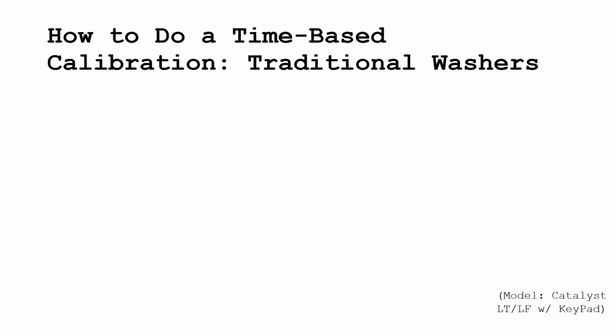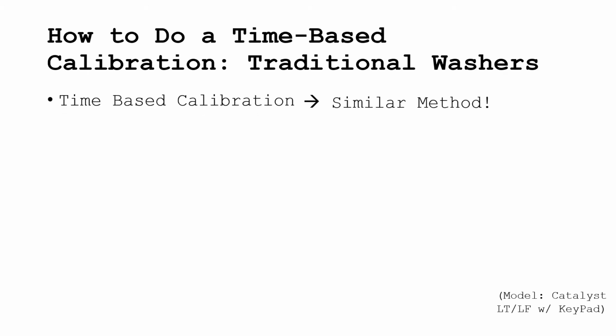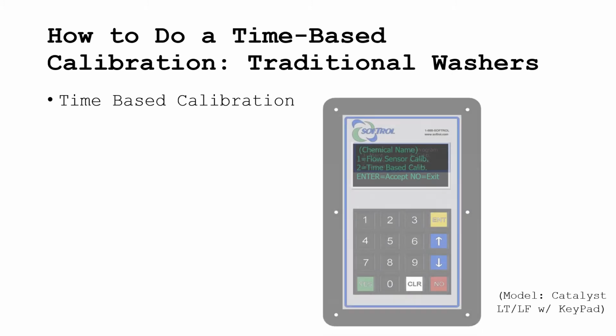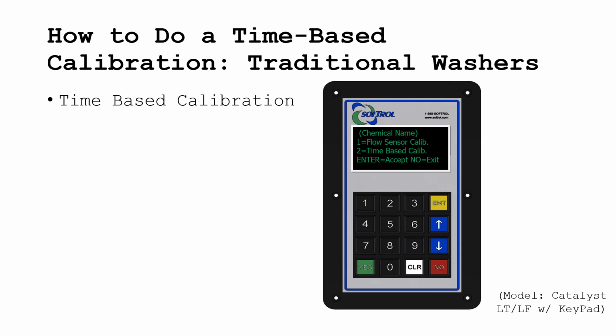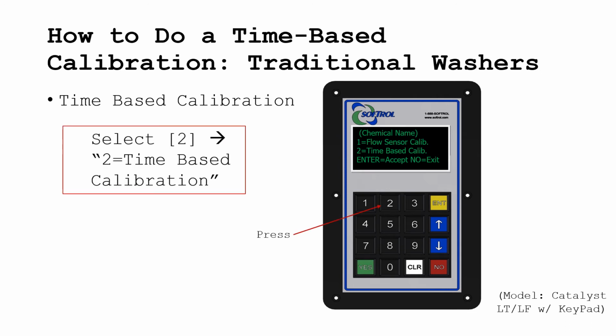To calibrate the chemicals on a traditional system without the flow meter, you use a very similar method as you normally would to calibrate. The only difference is, when you choose the type of calibration you want to do, you press the 2 key for 2 equals time-based calibrations to calibrate without using the flow meter.